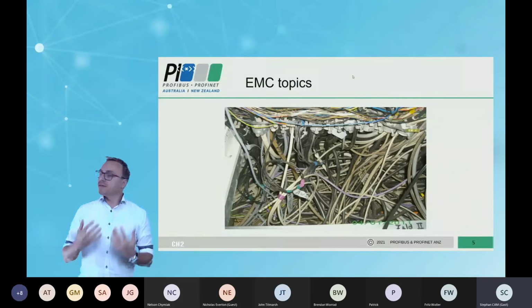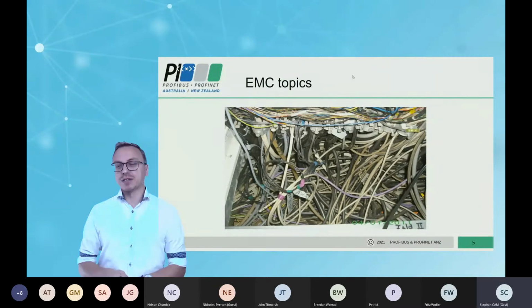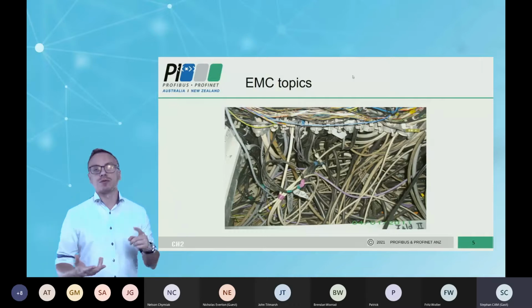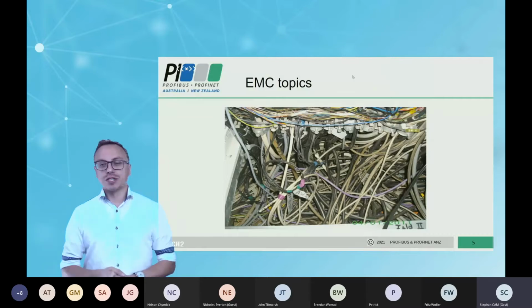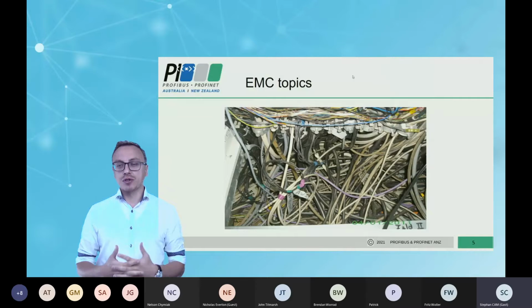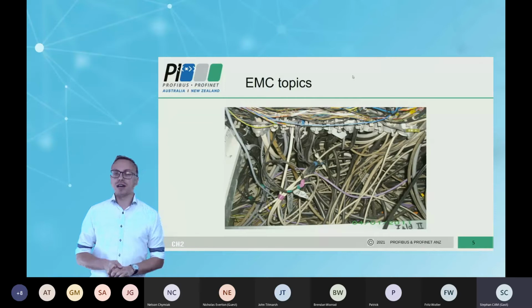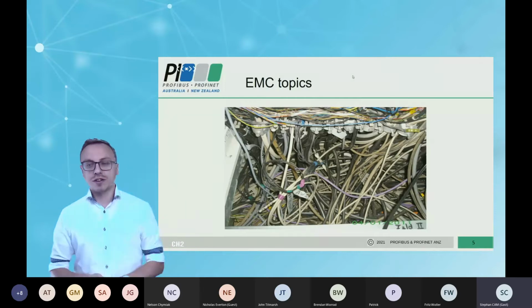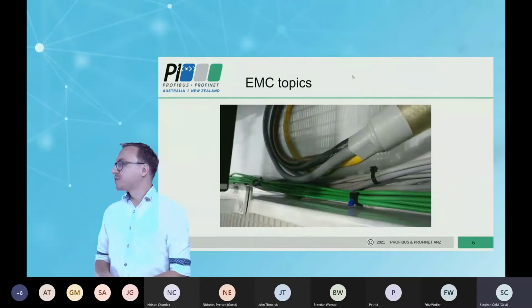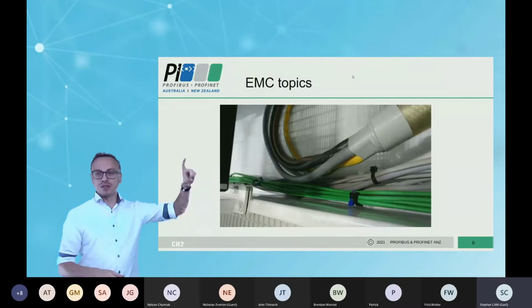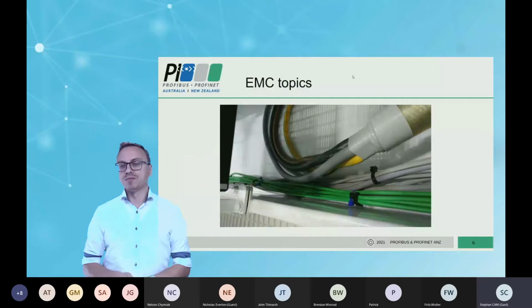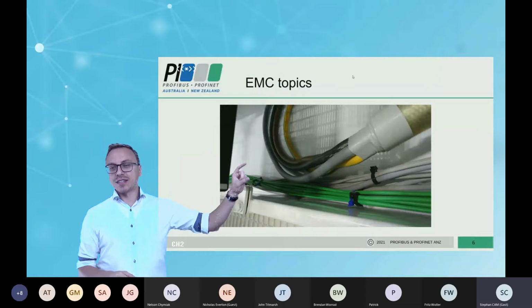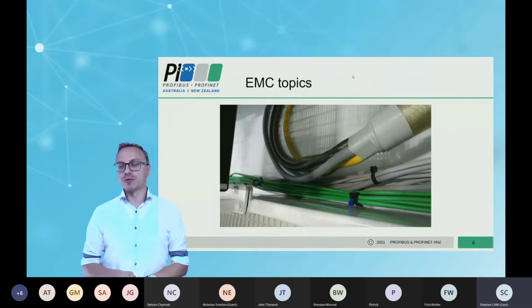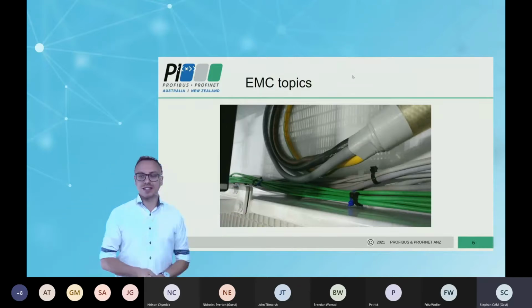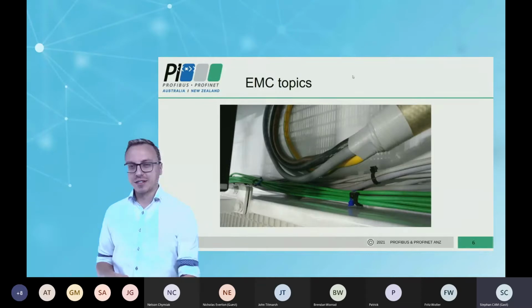But you have to say you have a good protection in EMC by the field bus system itself. That means you have a shielded cable, it's twisted pair, or it's a star quad cable, or you can say you have a voltage differential signal, and this means you have a good protection, but sometimes it's not enough if you have a lot of leakage current or potential equalizing current. So what else? Here you see a PROFINET installation very close to the motor cable or power supply cable. Normally you need a distance of 10 up to 20 centimeters to have a protection between cables like that and the data cables. And here you see, from a practical side, how it looks sometimes.